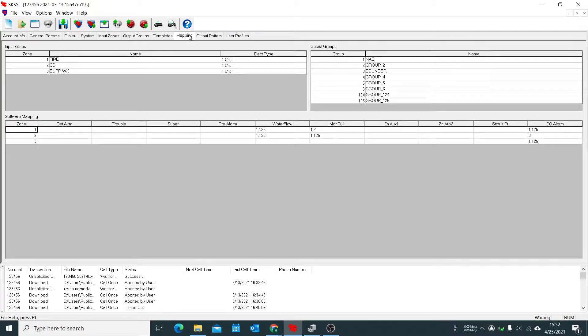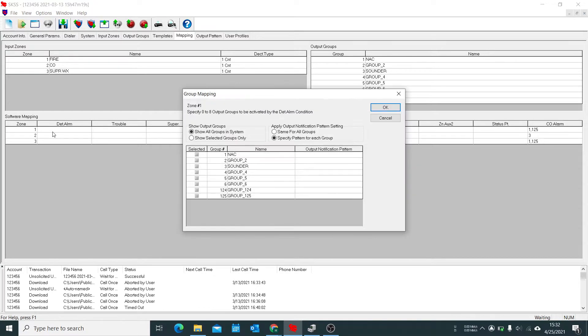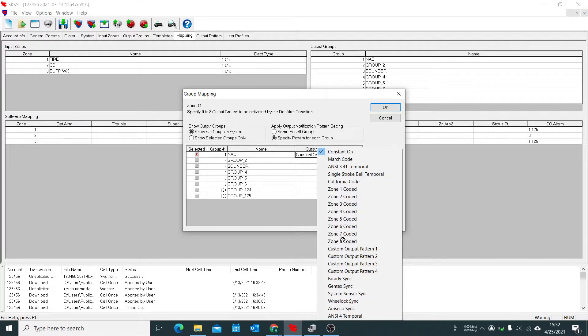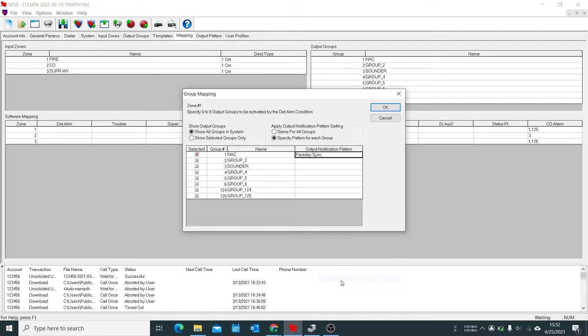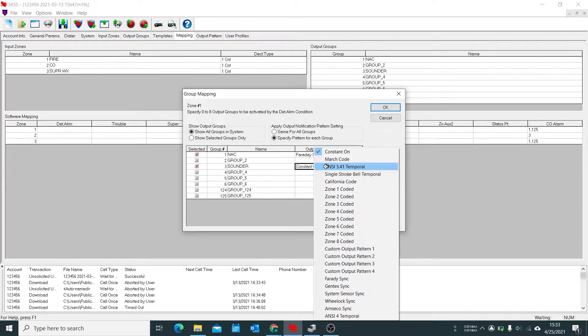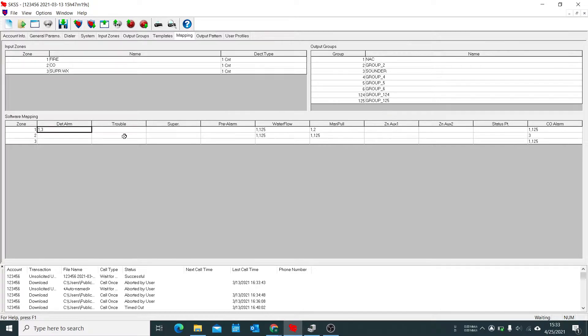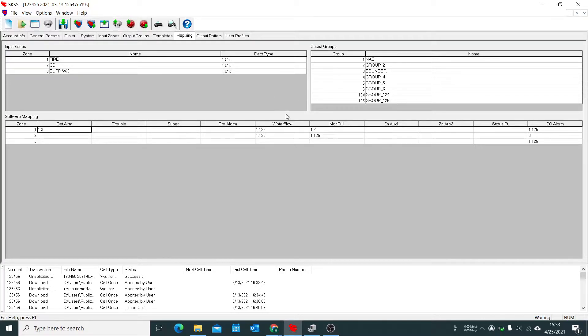Now at mapping it's great because it shows us our zones, our groups, and both of them together. So as we said group one is fire so we want that to activate NAC one or the NAC, and we want that set to Faraday sync. We also want the sounder to activate but we want that at code three temporal. And you have to repeat that for each device. So in this case I would have to do the same for detector alarm, water flow, manual pull station, and so on.